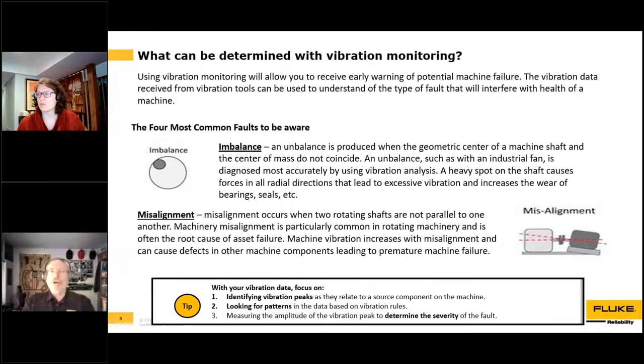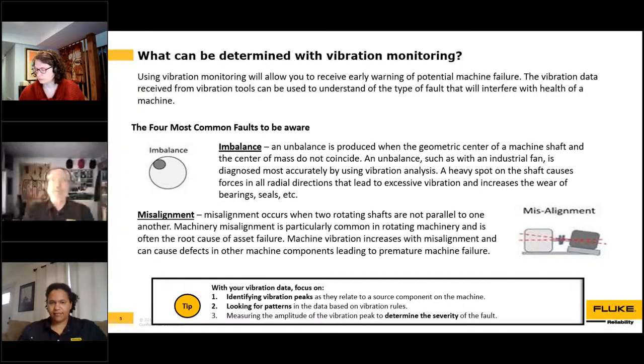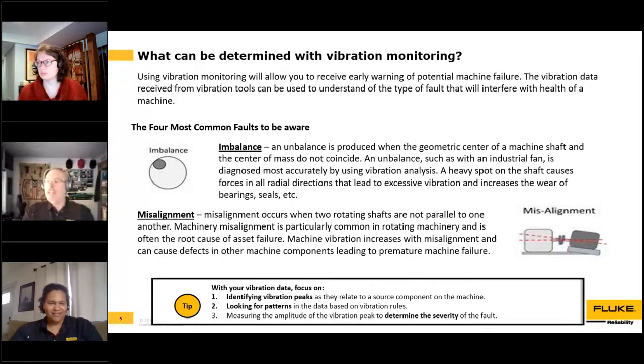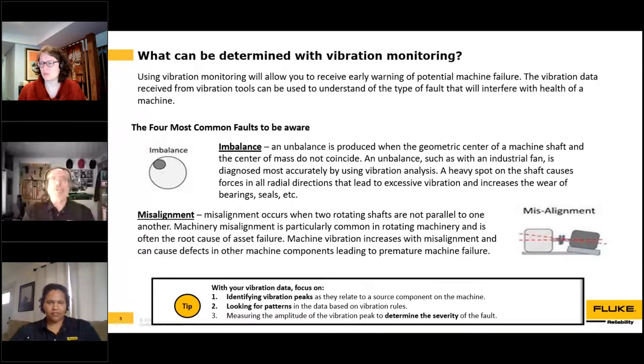How can we use vibration to look for faults in rotating machinery? Over the years, we've learned there are really four main faults for rotating machinery — we call these the big four. I saw these big four each and every day when analyzing data. The other faults — there are thousands — but we just don't see them that often. So the big four are: imbalance, misalignment, looseness, and bearing damage.